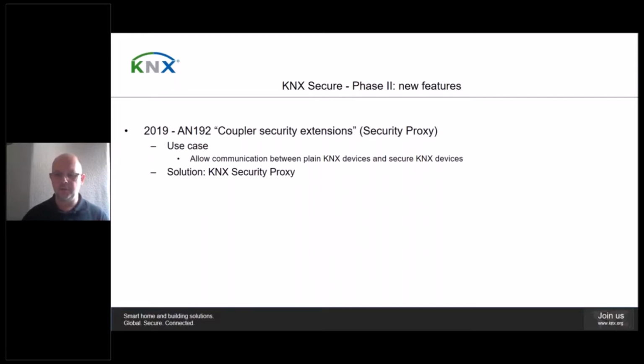The secure devices are a part of the KNX network protected with KNX Secure, e.g. on radio frequency, or an outside TP1 line. The plain devices are on a part of the network that is assumed sufficiently safe, e.g. built in the wall. The solution to this communication challenge is the KNX Security Proxy. The KNX Security Proxy is a coupler extension. This is an extension that can be added to the coupler by the manufacturer.